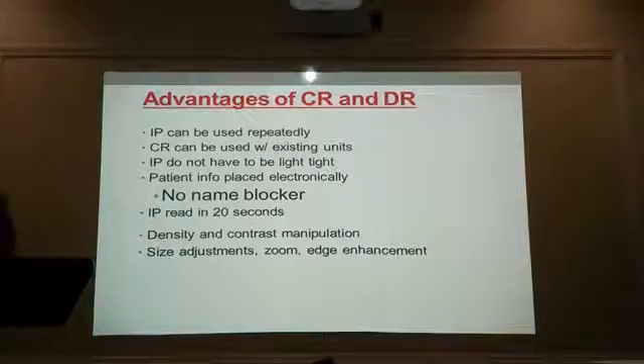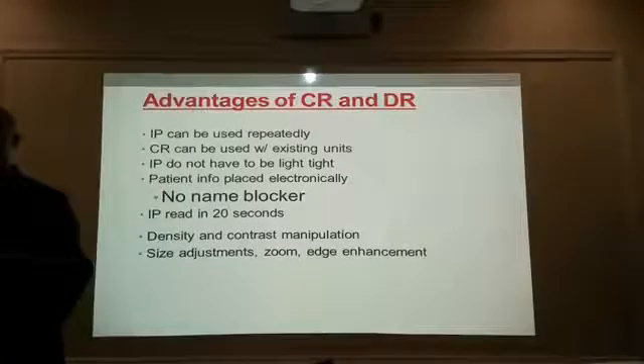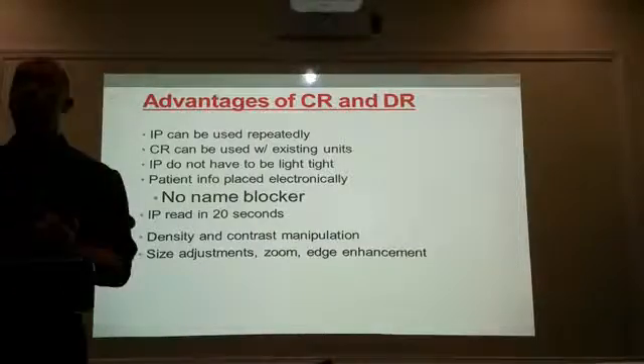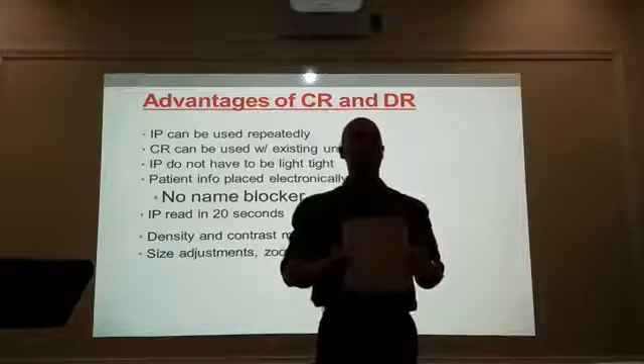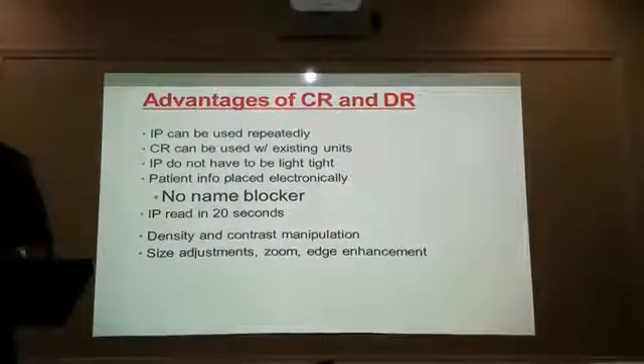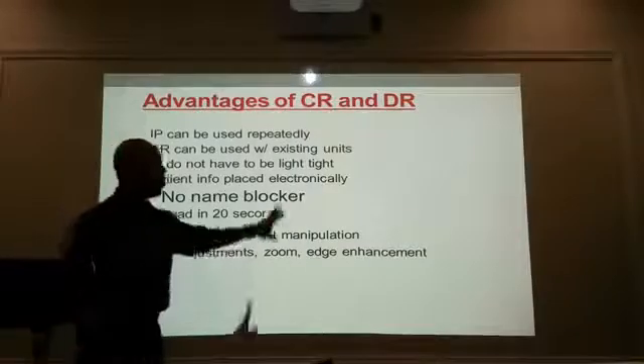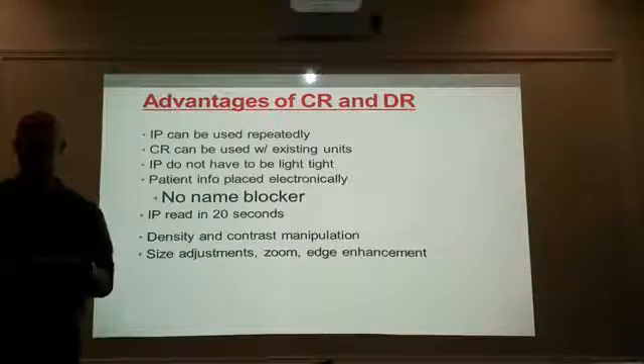So the difference and advantages between computerized radiography — here's a new term: DR. DR stands for direct radiography. With computerized radiography, we're using imaging plates that still have to be processed through the reader. With direct radiography, there are no cassettes. You take an X-ray and the sensors are in the table or on the chest board, and the signals go straight directly into the software program — your images come up simultaneously on your screen. That's direct radiography.